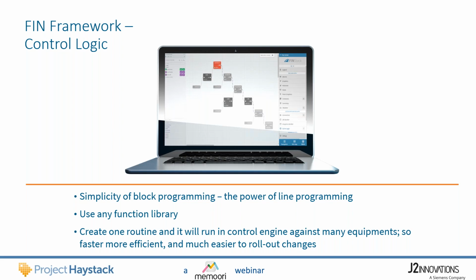So that logic gives you a lot more capability. You do it once, and then you can apply it across the whole site. You can also use that same relativization for fault detection diagnostics, creating logic that automatically looks for faults and does edge analytics on your project.